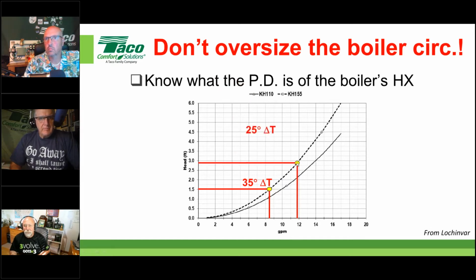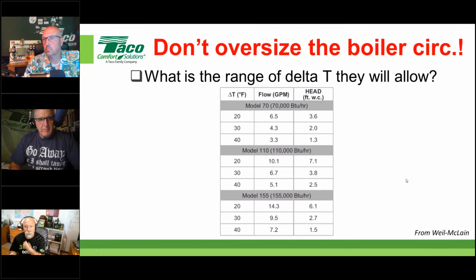I'm going to throw these all up there and point out that even at a 20-degree delta T, you don't have a lot of pressure drop through that heat exchanger. Just note that it's always listed in the manufacturer's information, and this is typical of many manufacturers. I'm just showing you a couple. Here's one from Weil-McLain. In this case we have that 155 boiler, and they're showing you a 20, a 30, and a 40-degree delta T. So this is in writing, this is what they'll allow, and this is what they're telling you to anticipate.